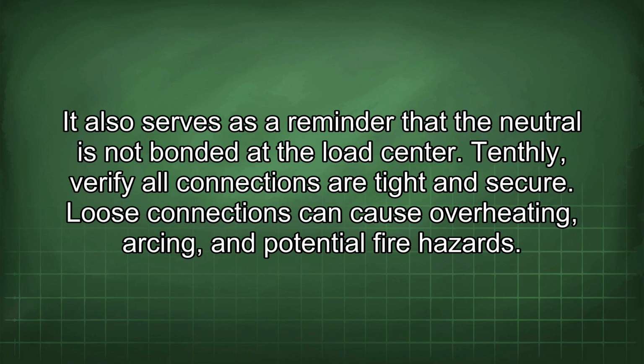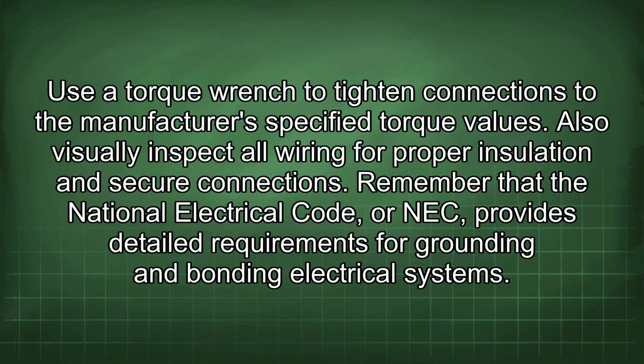Tenthly, verify all connections are tight and secure. Loose connections can cause overheating, arcing, and potential fire hazards. Use a torque wrench to tighten connections to the manufacturer's specified torque values. Also visually inspect all wiring for proper insulation and secure connections.